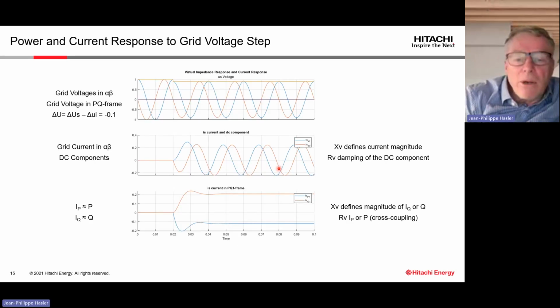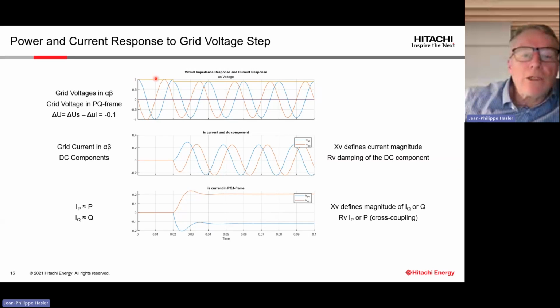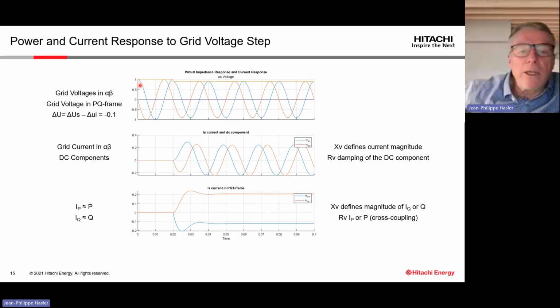Just to show a very simple example of how the STATCOM should react when we have a voltage decrease in the bus voltage: the yellow curve here is a voltage step from 1 per unit to 0.9, shown in alpha beta, and this is how the voltage behaves. What you see is only a sudden change in magnitude. And you see the direct contribution from the STATCOM. The current generated is only defined by XV and RV, the virtual impedance. We have an almost instantaneous response of the current, almost no delay.